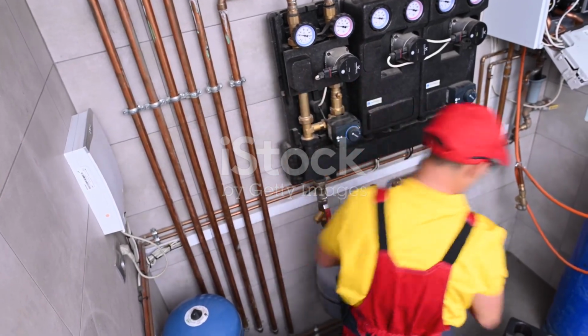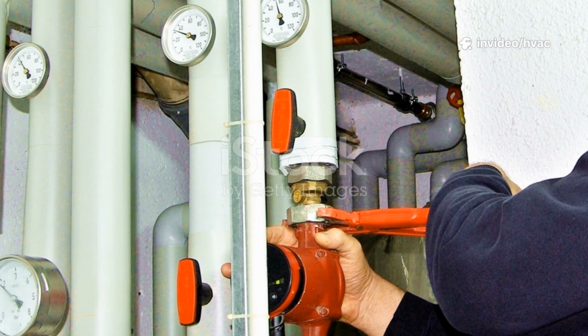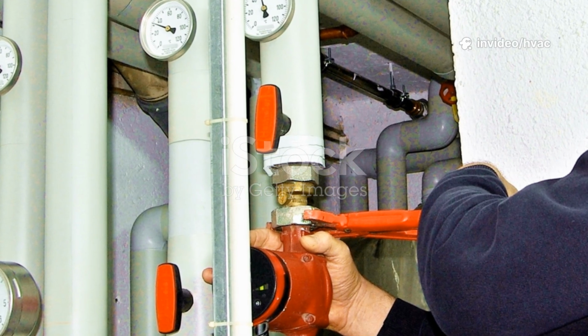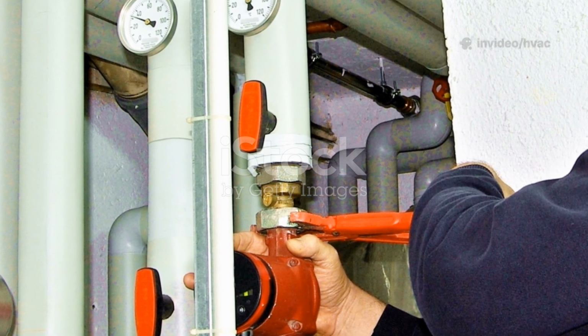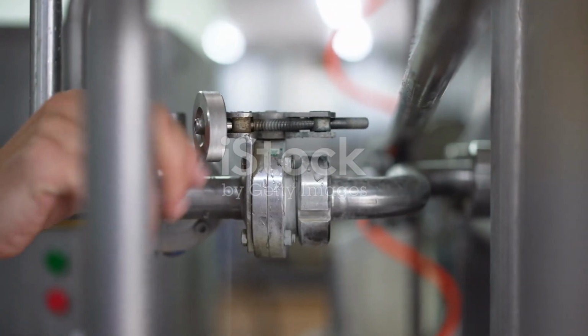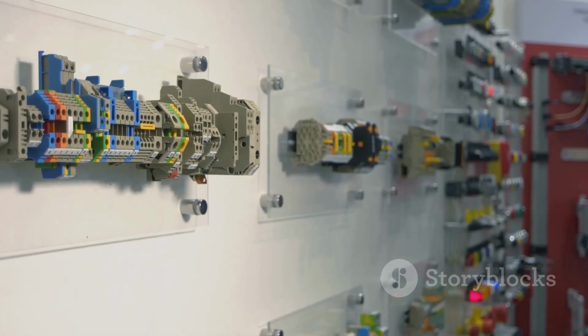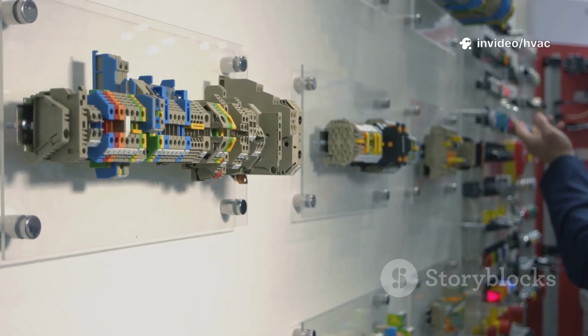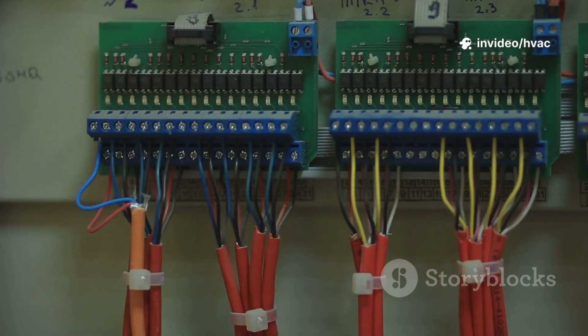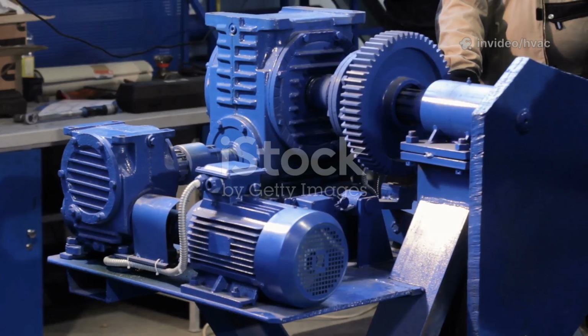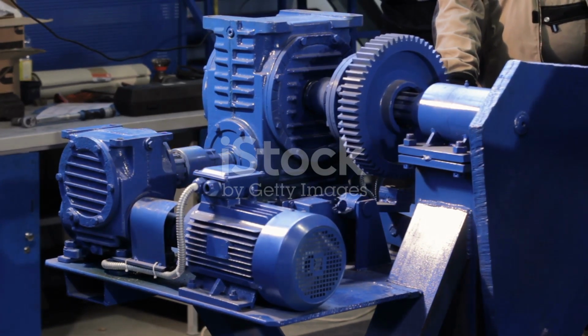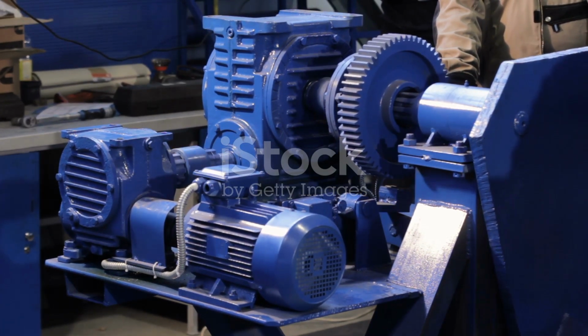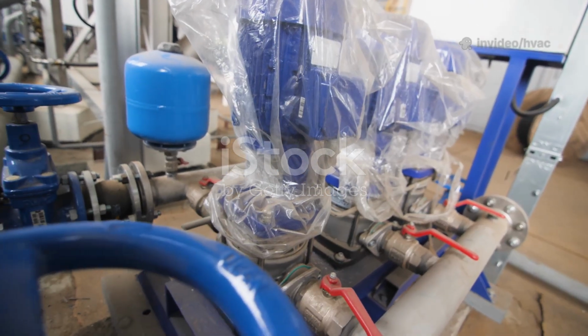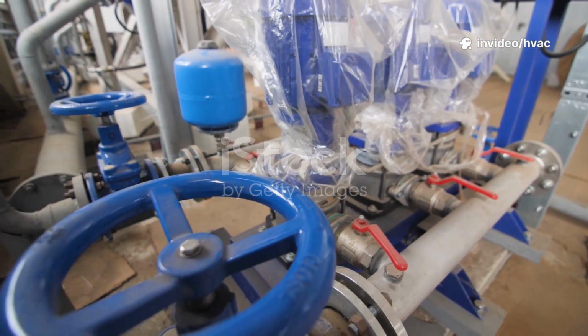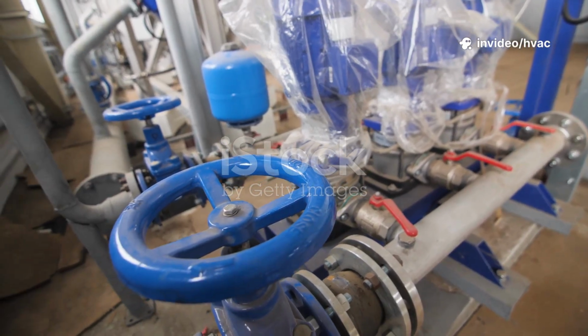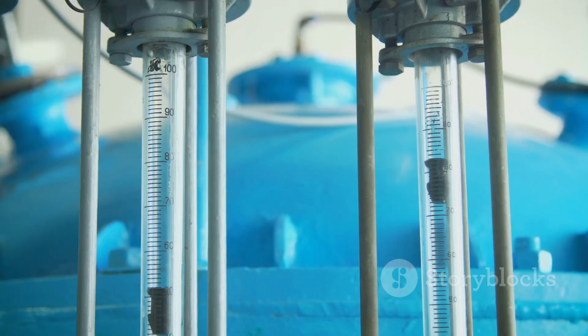Integrating PICVs with a building automation system, or BAS, is a straightforward process that really unlocks their full potential for energy efficiency and smart control. The PICV's actuator is the key component for this integration. Most modern actuators are designed to accept standard analog control signals from a BAS controller. The most common signal types are 0 to 10 volts DC or 4 to 20 milliamps. In a typical setup, the BAS sends a signal to the actuator, where 0 volts, or 4 milliamps, corresponds to the valve being fully closed, and 10 volts, or 20 milliamps, corresponds to the valve being fully open to its preset maximum flow rate. This allows for precise, proportional control.